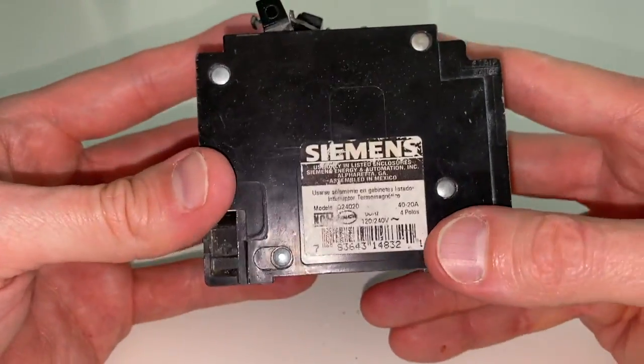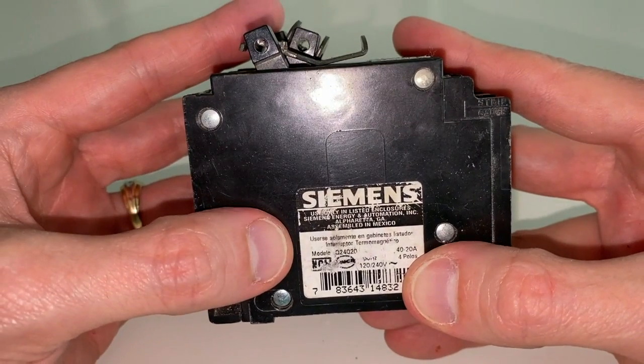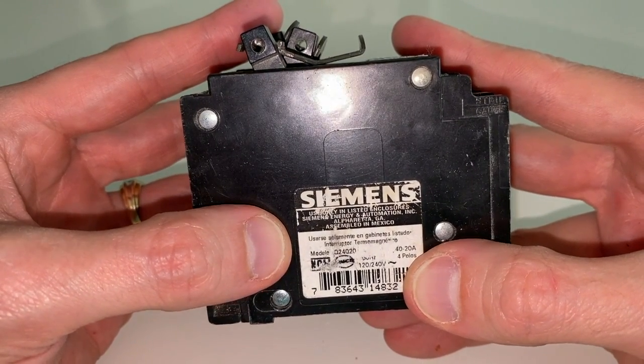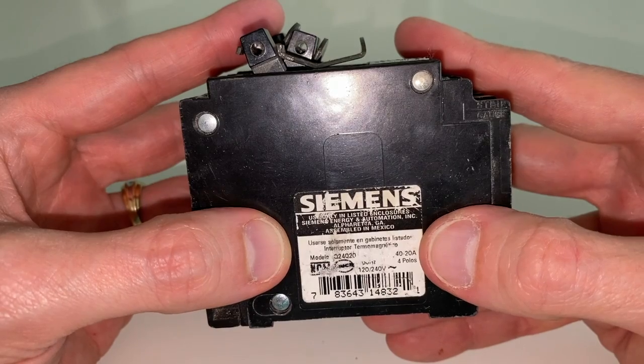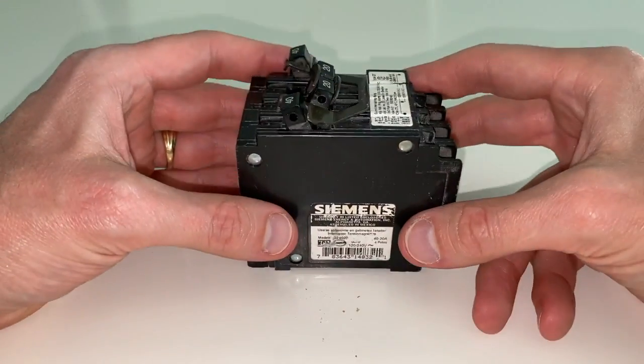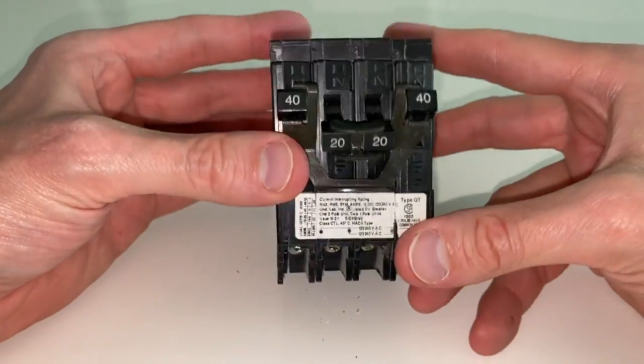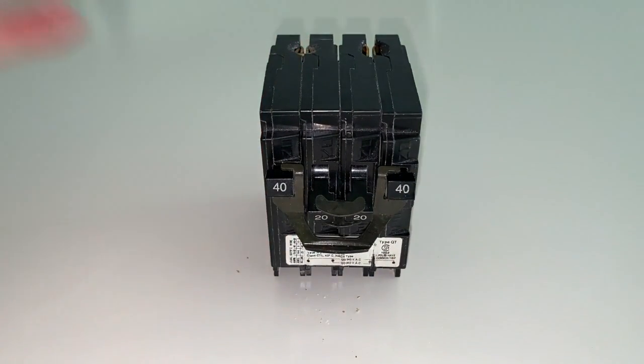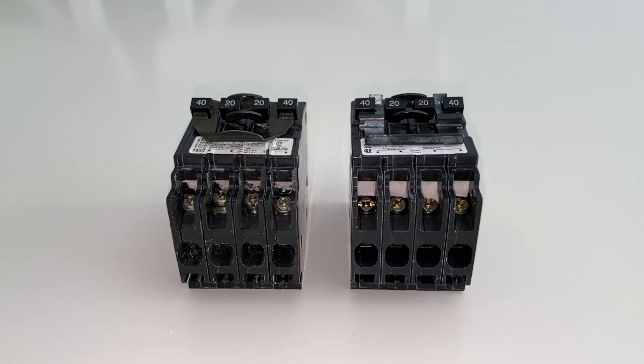And again, using this information here, in our case, model number Q24020, and all the way over here, 40-20 amp, 4 poles. From here, down below in the comments and description will be a link to replacement breakers, and we will go grab the new one and get it installed. We now grab the brand new circuit breaker, old one on the left, new one on the right, and again 40s on the outer, 20s on the inner, and just make sure everything is exactly the same.